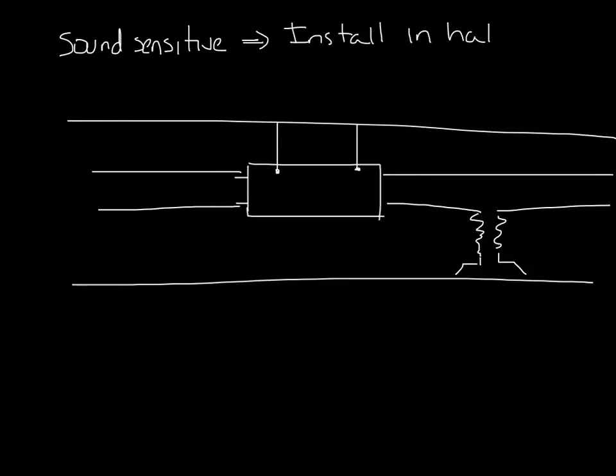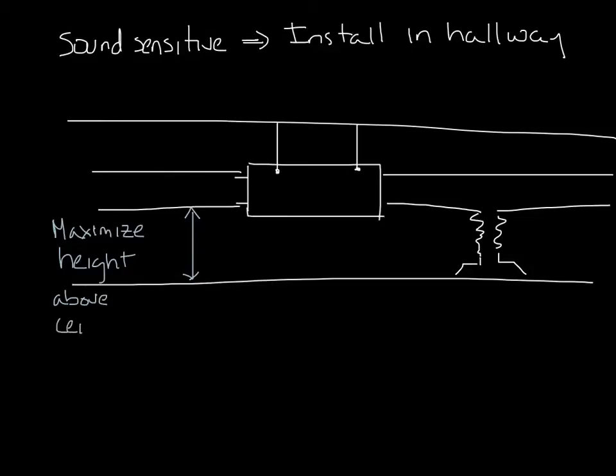If it's a sound-sensitive application, maybe a conference room or the president's office, you'll want to install the VAV box, especially if it's a fan box, in the hallway outside of the office. You should hang the VAV box as high above the ceiling tile as possible. We've seen that if the VAV box is within an inch or two from the ceiling tile, you lose the acoustical benefits of the ceiling tile, and ceilings attenuate a lot of sound.